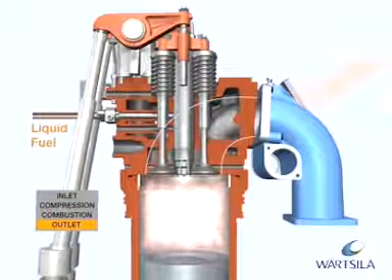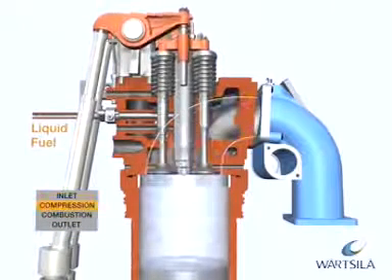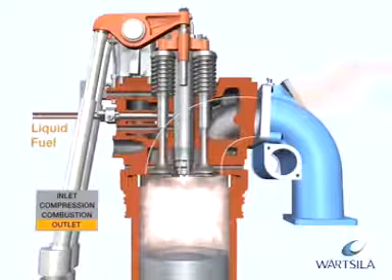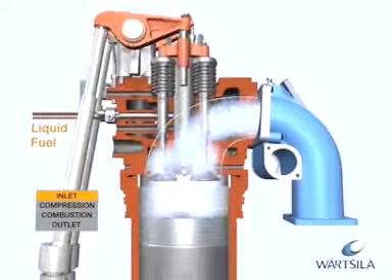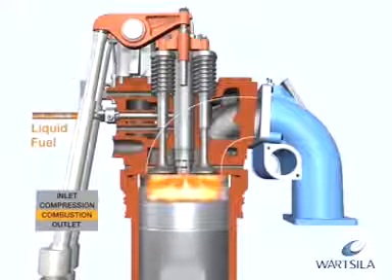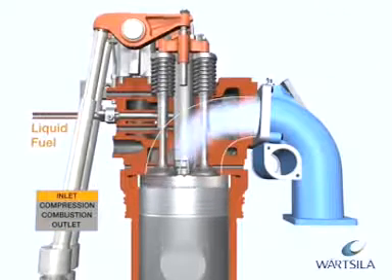After the working phase, the exhaust gas valves open and the cylinder is emptied of exhaust gases. With the piston in its upper position, the inlet valves open just before the exhaust gas valves close and the cylinder is filled with air. In Wärtsilä engines, the inlet valves close just before the piston reaches the bottom dead centre.